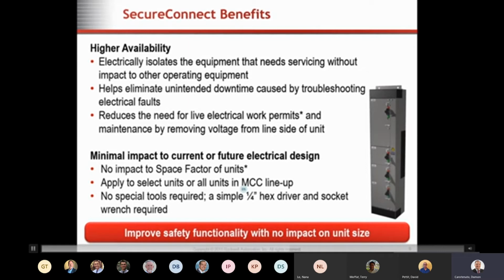Another thing to remember is anything over 180 amps puts it into a dual stab type of situation, and we do not have the technology yet to have a SecureConnect on a dual stab. So there are three things to remember. If you put an MCC lineup together, you may end up having some buckets that can have SecureConnect and some that can't, depending on your elevations and current ratings - three reasons you may not be able to get a SecureConnect on your MCC bucket.